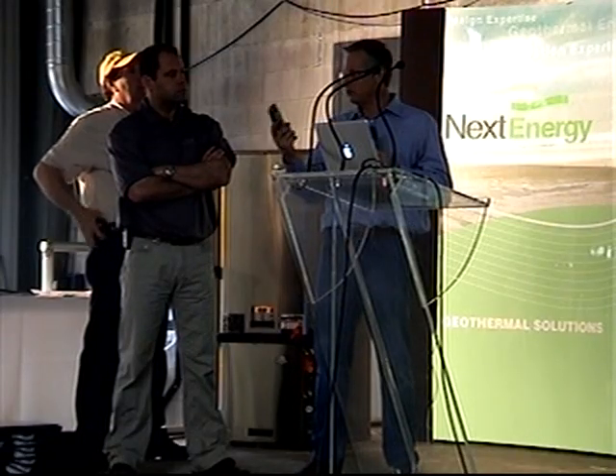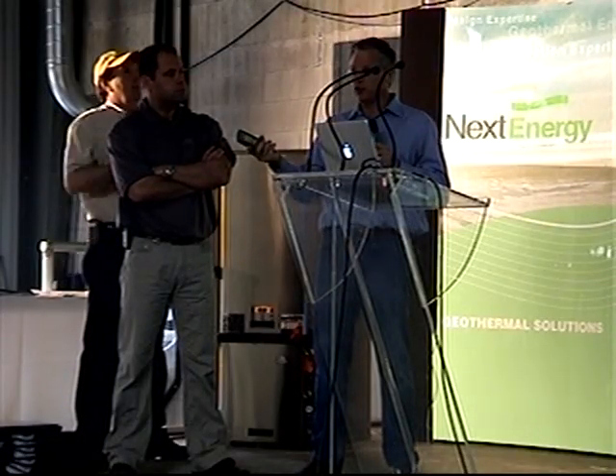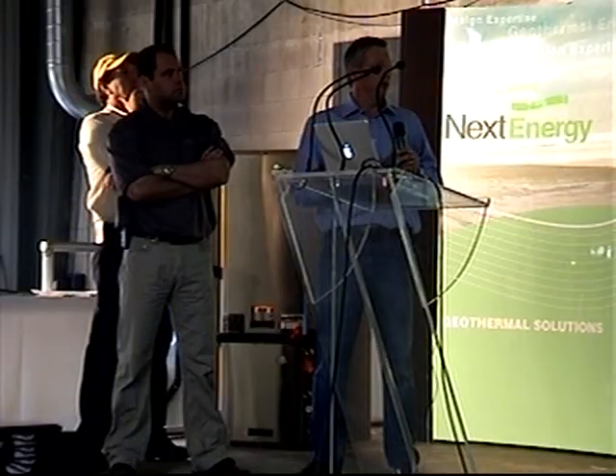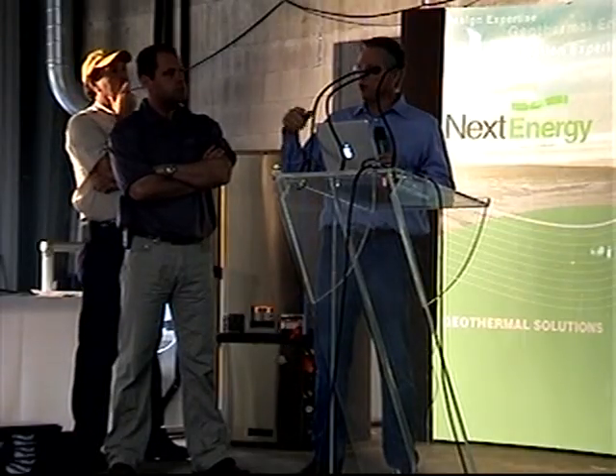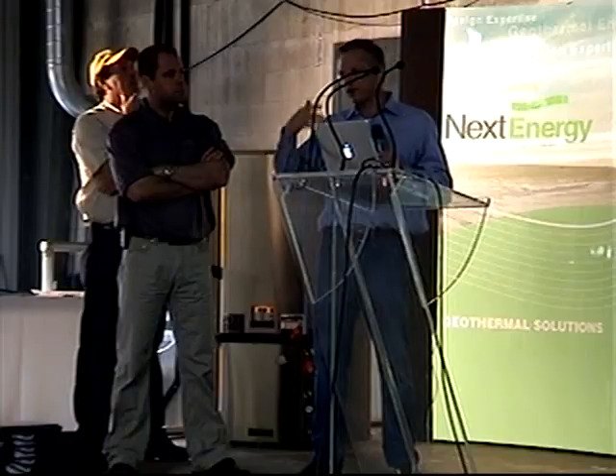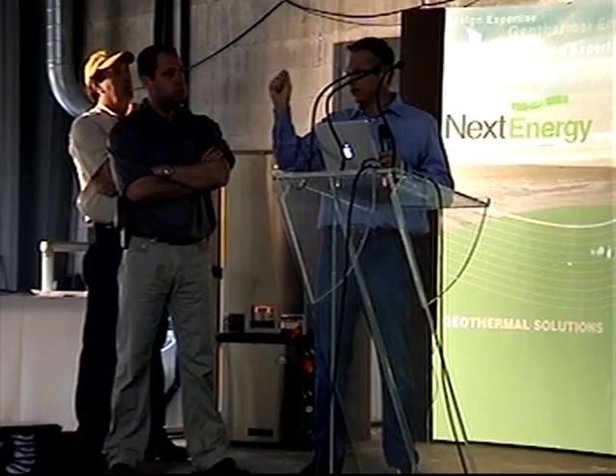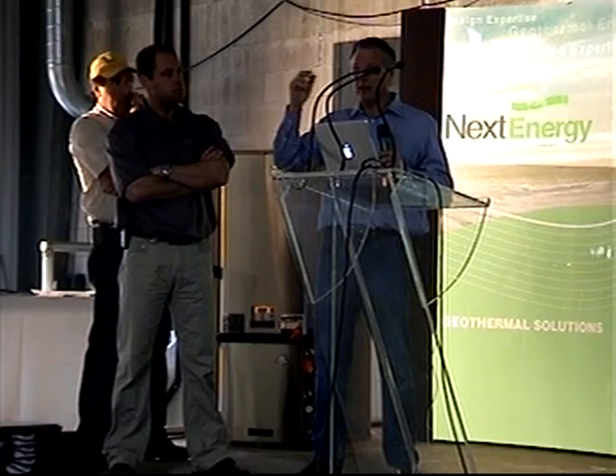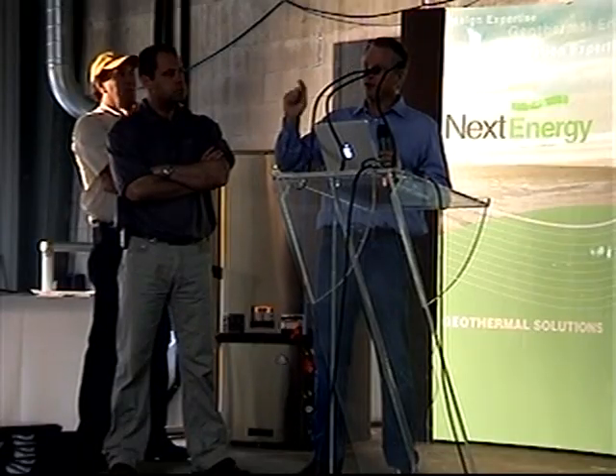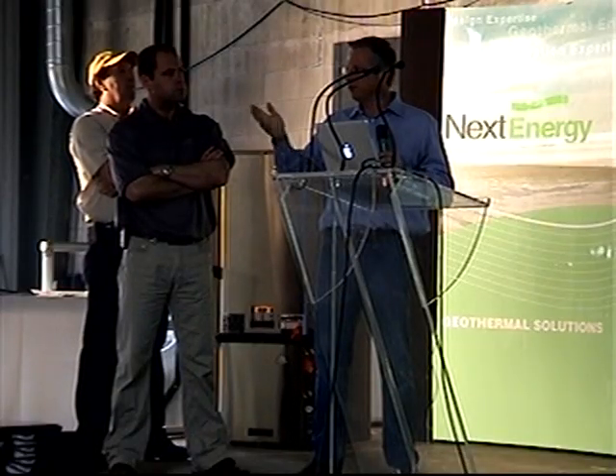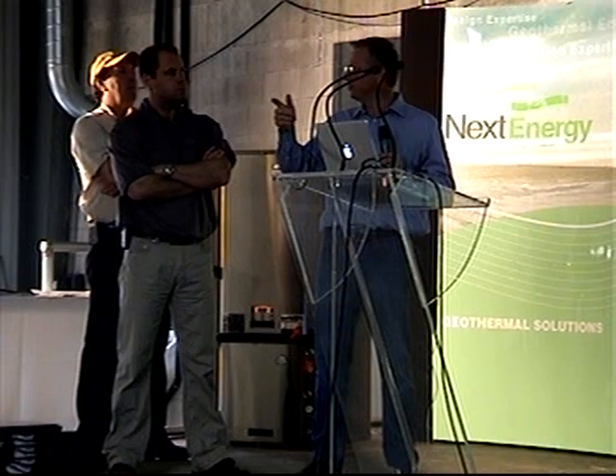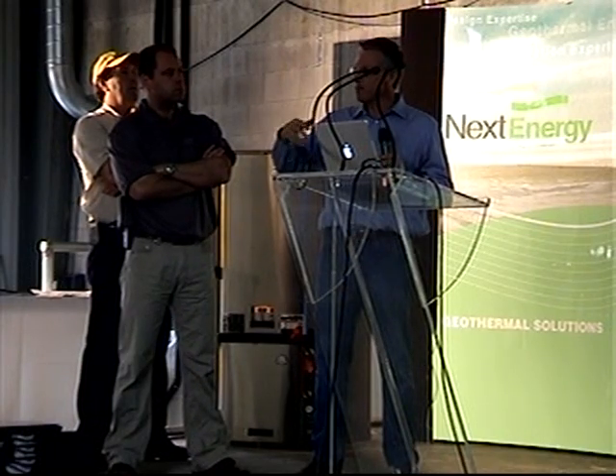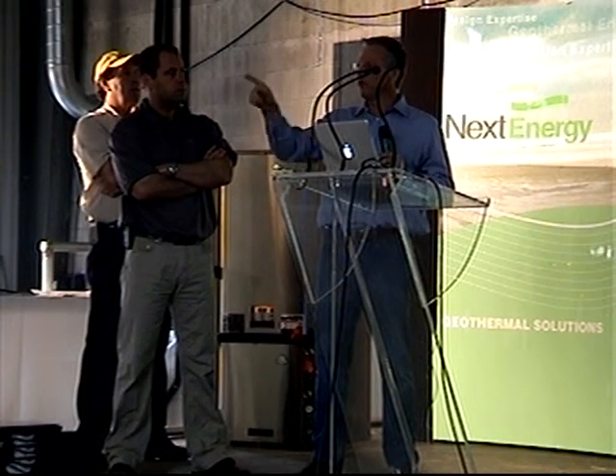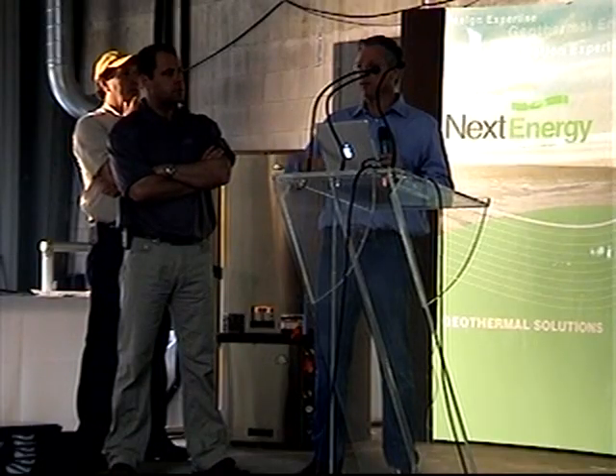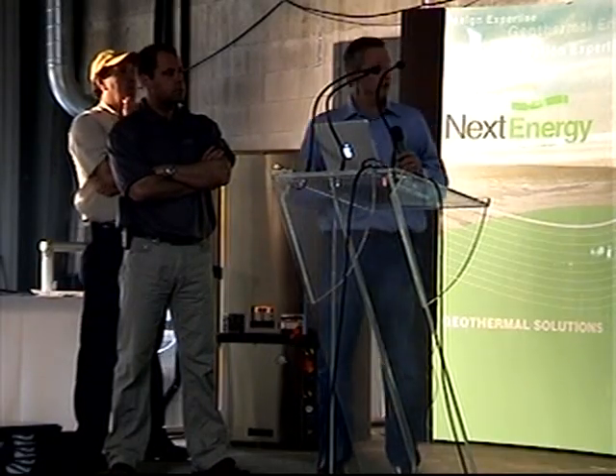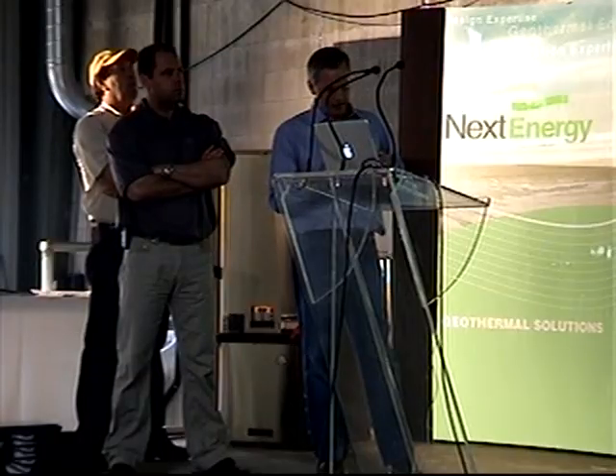So if you're at the board, you just count the number of flashes. That'll tell you the cause of the fault. If you're at the thermostat, you can do this over the phone with the homeowner. They're calling you up: my unit's shut off. You know, the fault light's steady, locked out. You just tell them, okay, turn your fan off and on 3 times. If you do that 3 times within a minute or 2 minutes, can't remember the exact parameter, the unit will go into a mode where it then blinks the fault code right at the thermostat. Kind of a handy feature. So you can read it right at the stat.